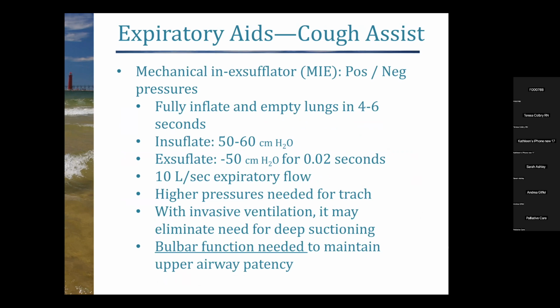Be aware, cough assist is something that exists. The technical term for it is the mechanical insufflator-exsufflator, and that's exactly what it does. It will insufflate the lungs to 50 to 60 centimeters of water and then rapidly exsufflate. So it drops from 50 to -50 in 0.02 seconds. That's an extremely high velocity for that pressure drop. And with the exit of all that air, it triggers a cough and helps pull up all the secretions that may be stuck deeper down in the lungs and the airway.